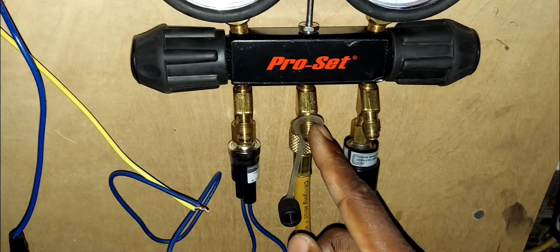And this yellow hose is a charging hose, right? The middle port is the charging port. So what I'm gonna do is have nitrogen charge pressure up into the gauge manifold while I open my high side valve, it will allow that pressure to go through, and I can trigger the switch - I could trip it, right?